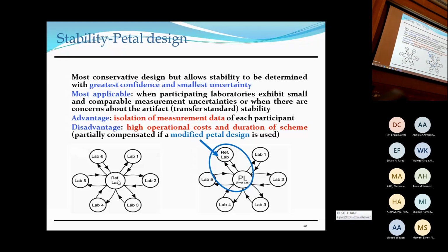It could be that besides the reference lab, so it won't have to do all of the work of stability measurements, there is also a pivot lab, as it's called, which basically has its standards calibrated by the reference lab, and then the pivot lab is the one that does the checking of the stability of the artifact as it's circulated back and forth between labs.